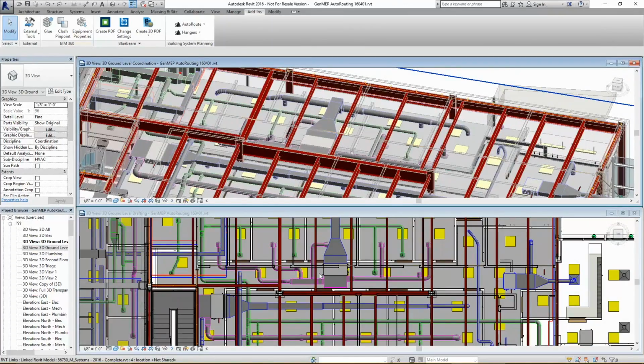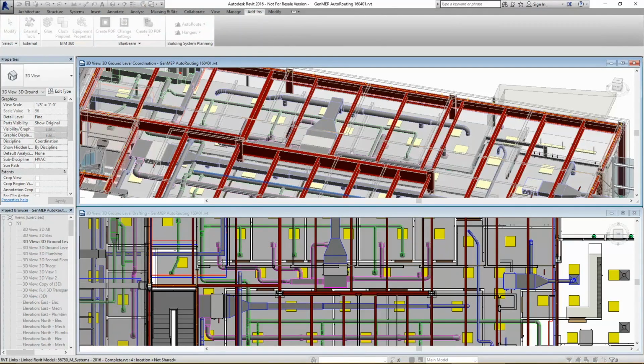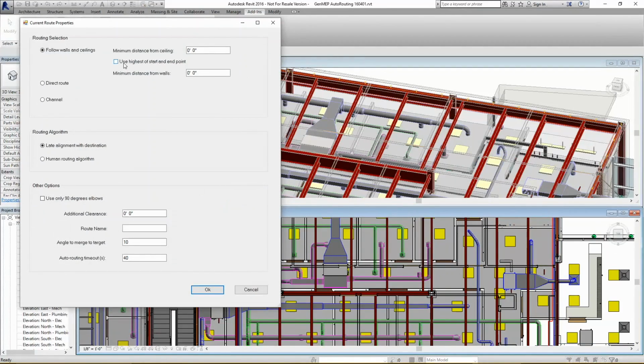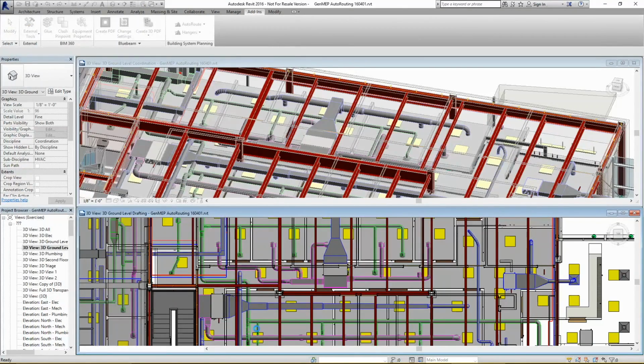We start by selecting the GUI autoroute function on the BuildingSP autoroute menu. Next, the endpoints of the start and end target stubs are selected. A window opens up that allows parameters and algorithms to be specified for the route. A clash-free conduit route is then generated as shown in red.